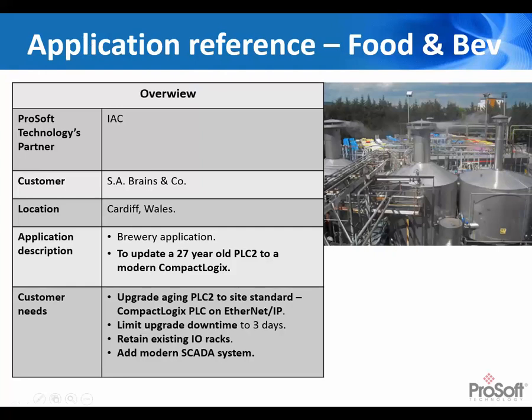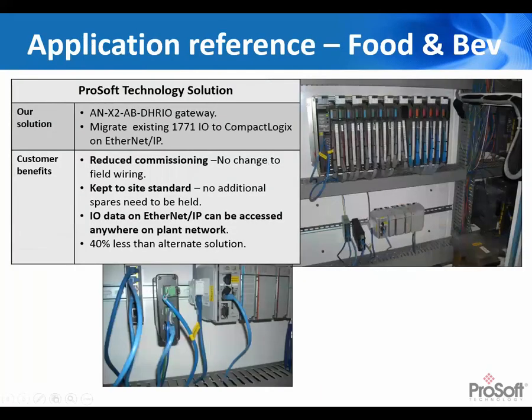So they retained their existing I/O racks but also added a modern SCADA system, introducing a migration gateway to keep the existing 1771 I/O racks. This reduced commissioning time, required no changes to field wiring, kept everything to the site standard with no additional spares needed anywhere, and allowed the I/O data to be accessed from anywhere on the plant network over Ethernet IP. It was also 40% less than the alternative solution.